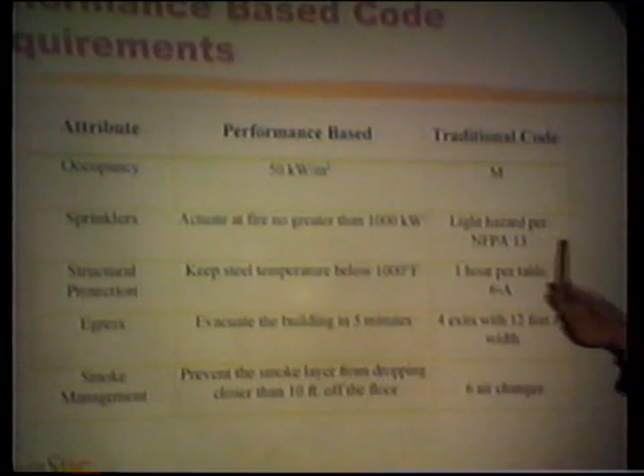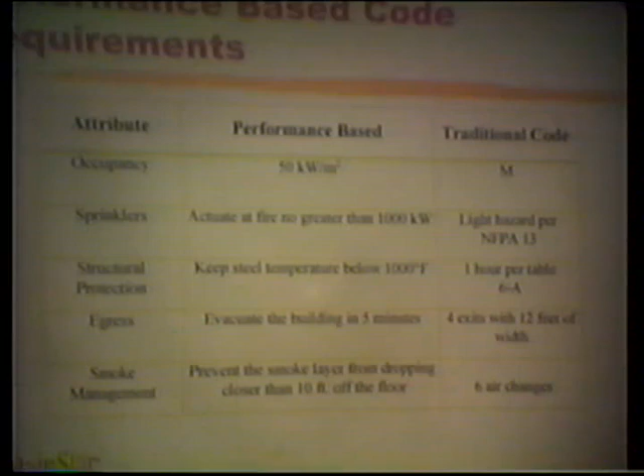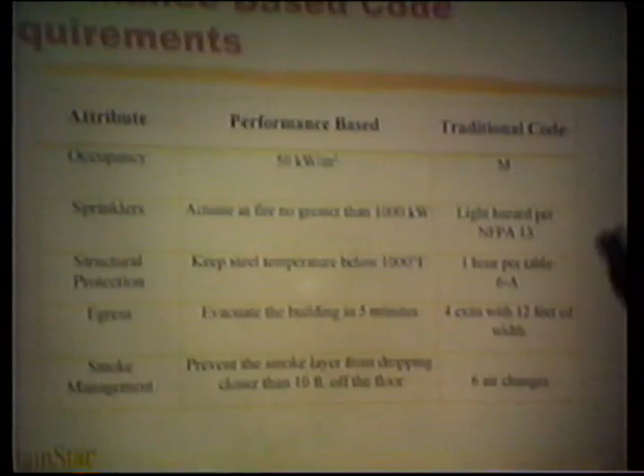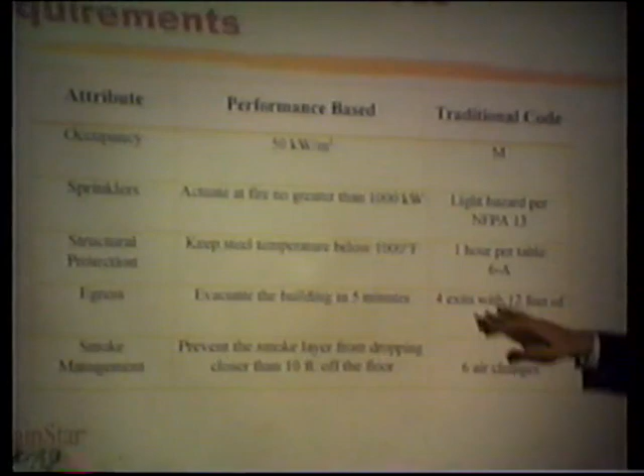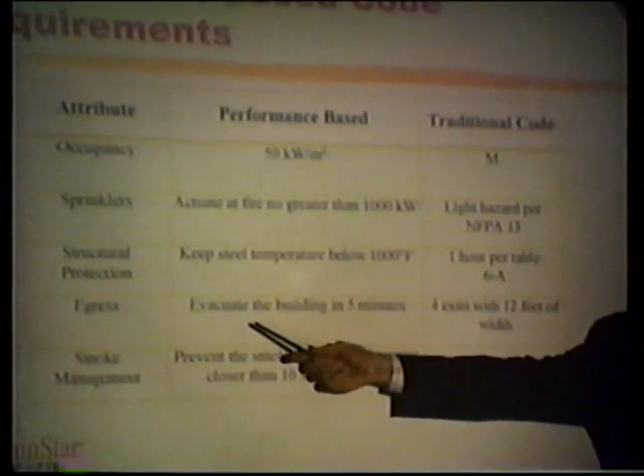Okay, we might say something about sprinklers. Well, we're going to put in a light hazard sprinkler system in accordance with NFPA 13. We may say we want the sprinklers to be designed so they actuate when the fire is no greater than 1,000 kilowatts. Structural protection. The code might tell us, well, we need 1 or 2 hour protection per table, blah, blah, blah. Well, we might say, just demonstrate in that building that we can keep the steel temperature below 1,000 degrees Fahrenheit. With egress, the code will tell us, well, we have a certain occupant load, we need so many exits with so many feet of exit width. Here we might state, well, let's demonstrate that we can evacuate the building in so many minutes.